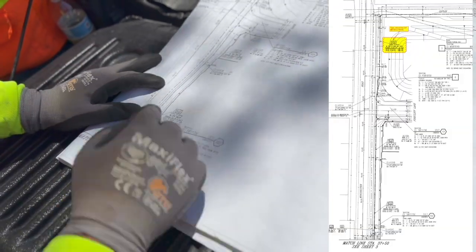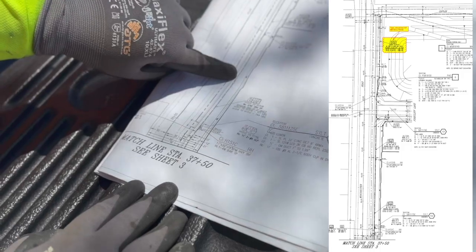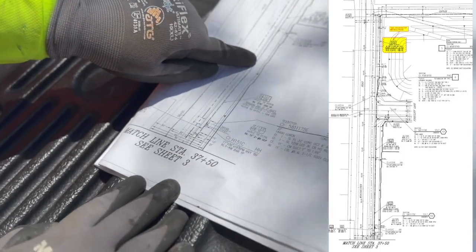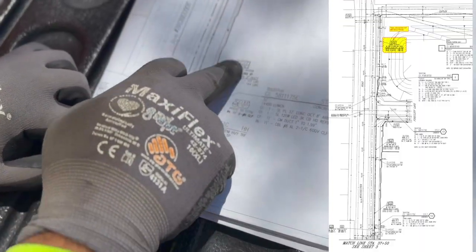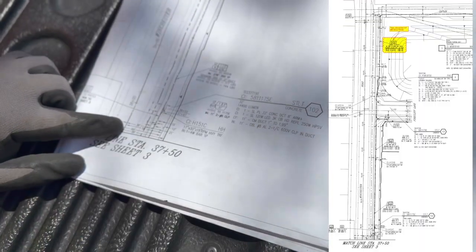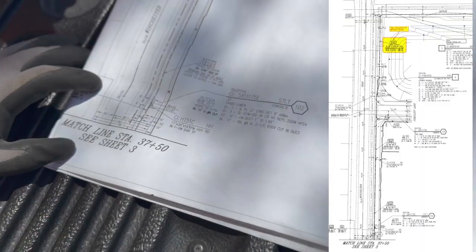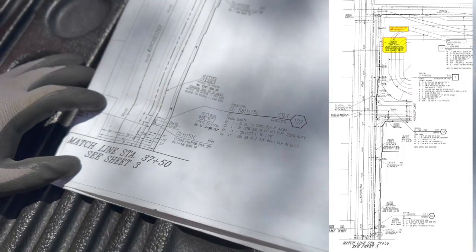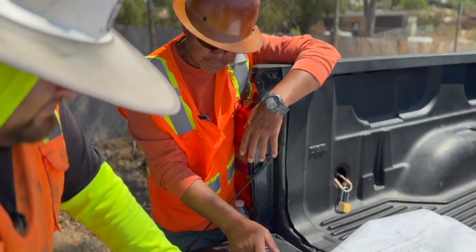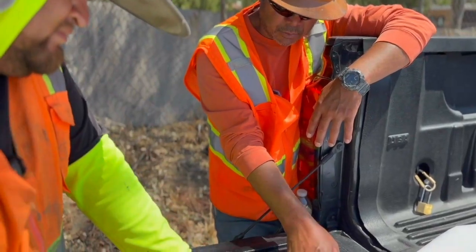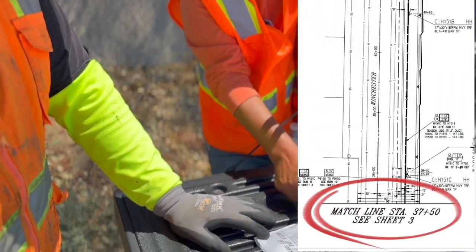And then, as you can see, the solid trench, solid black line, or that's dotted, my bad. It keeps going down, and you have more callouts. So that's indicating everything that you're placing in the same trench, and that way you know there are multiple things that you put in it. Yes. Okay, yeah, because I see another note right here with a memo, so that means there is something else.